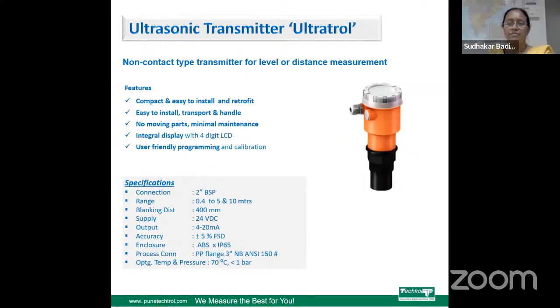And this is an ultrasonic level transmitter. This is a non-contact type transmitter, which is used for level and distance measurement. Very compact and easy to install and retrofit. No moving parts, hence no maintenance. It has an integral display. The programming is user friendly and calibration can be done very easily. It is available for the range up to 5 meters and 10 meters. Blanking distance is 400 mm. And the enclosure is ABS IP65. The accuracy will be plus minus 0.5%. And it's suitable for a maximum temperature of 70 degrees Celsius and pressure of 1 bar.